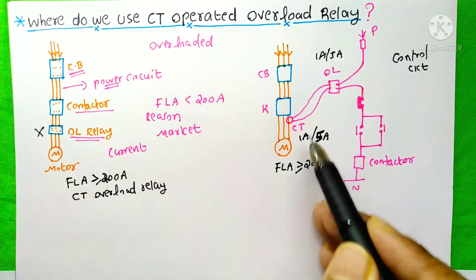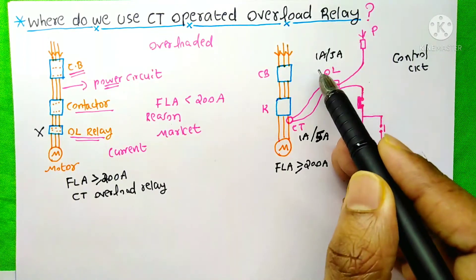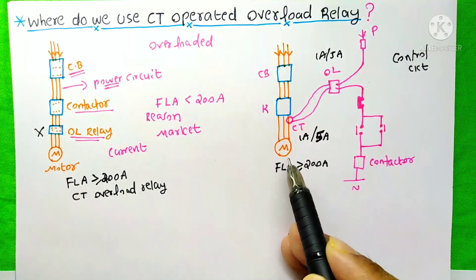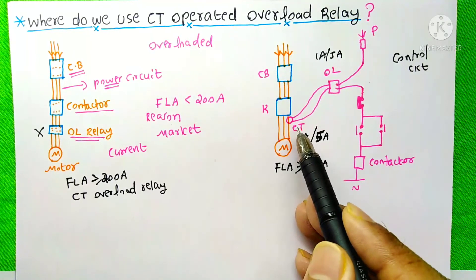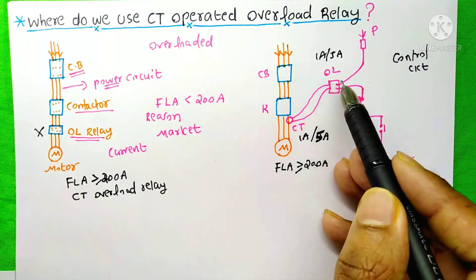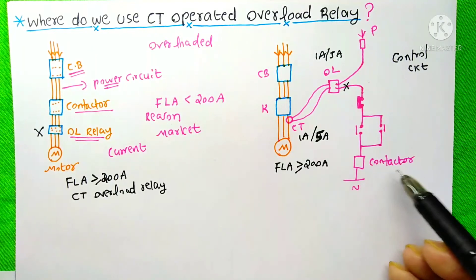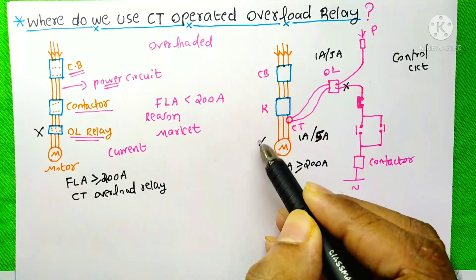But here, this overload relay's capacity only depends upon this CT's secondary current. If this motor consumes more current than its rating, then this CT sends signal to the overload relay and this overload relay trips. And this contactor will not get the power and the power to this motor will be cut off.